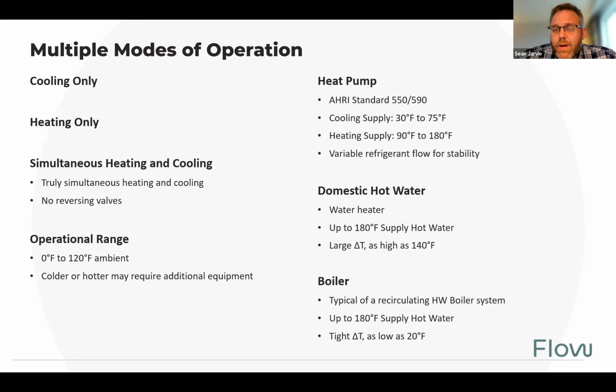Normal heat pumps that are on the market that you can buy commercially today are rated by an AHRI standard. It's 550/590. That's the way the energy code's written, and they classify all the variables for heat pumps. So with this, the systems we're designing today have an operational cooling range from 30-degree water systems all the way up to 75-degree water. And on the heating side, we can heat up water from 90 degrees all the way to 180 degrees. We use variable refrigerant flow for high stability of all those loads, and we can operate them independently.